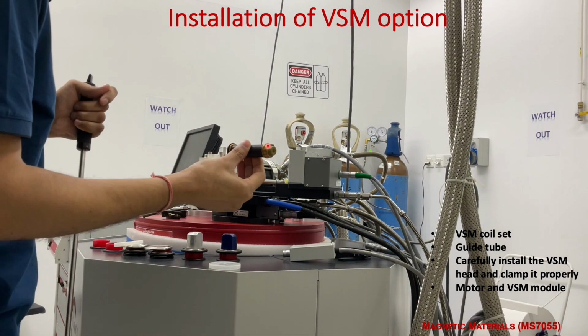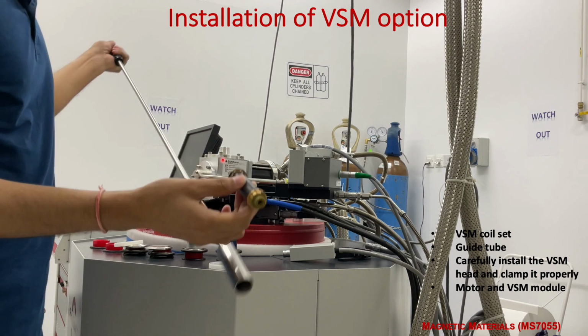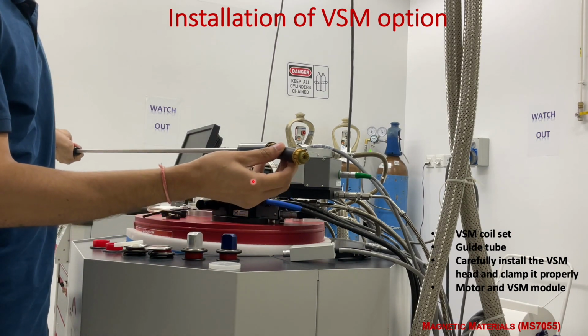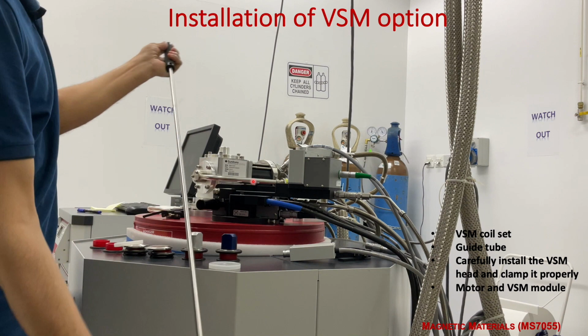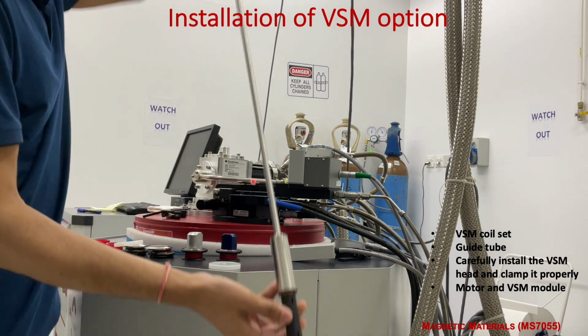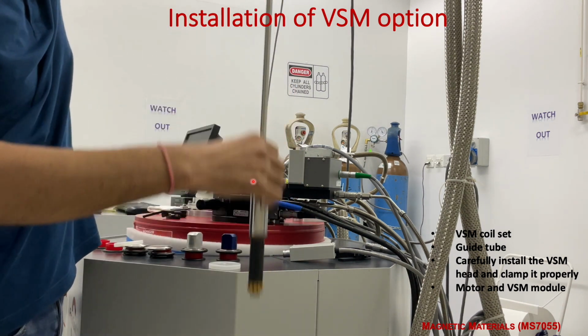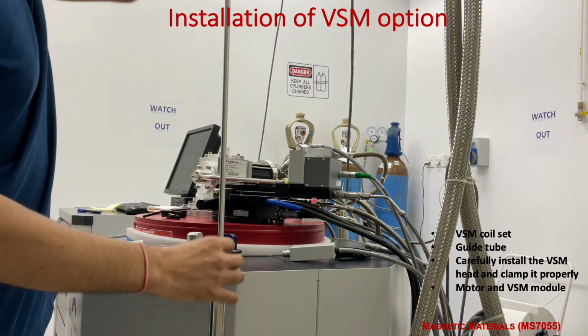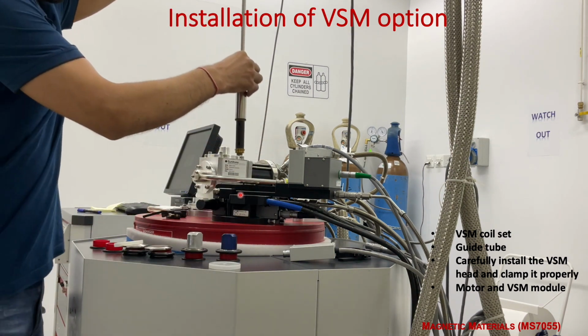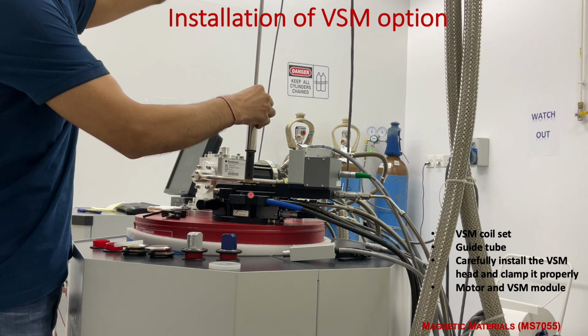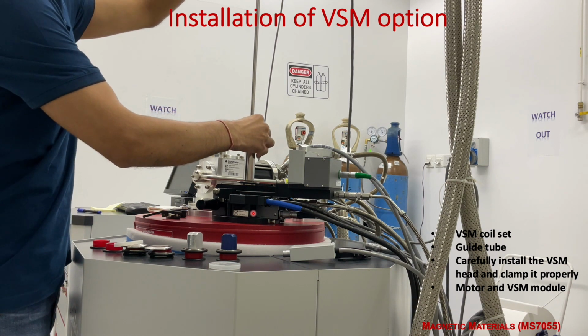So this is the pickup coil. Then I'm installing it using this tool. This tool can clamp it from the top, and it will not fall down unless you loosen it from the top. So now the coil is going inside the chamber.